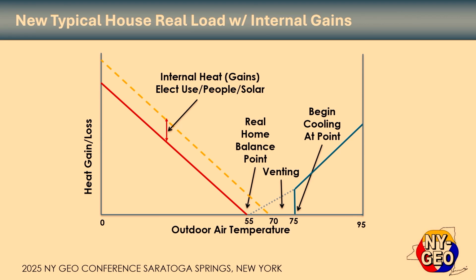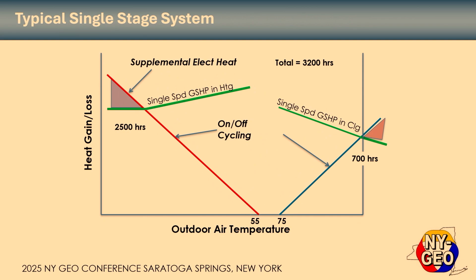So again, going back to our chart, you can see the red line has been shifted down to about 55, and we're going to be looking at these load lines a lot today to try and predict when electric heat and all those things are going to come on. And you can see the cooling load line there on the right, the blue line. We've adjusted that for those internal gains and electric use, people, solar, all of that is where that comes from. So let's take a look at what a typical heat pump system would look like.